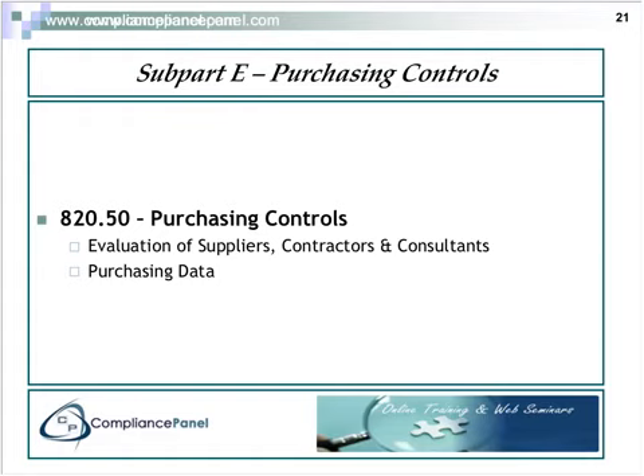Purchasing controls. It's important for all of you to understand that any materials or services that are used in the manufacture or processing of the device must be purchased from well-controlled suppliers. And this has become a big point in the FDA's audit activity because so much material is being outsourced outside of the country. So they're concentrating a lot more on your supplier controls, how you control your suppliers.